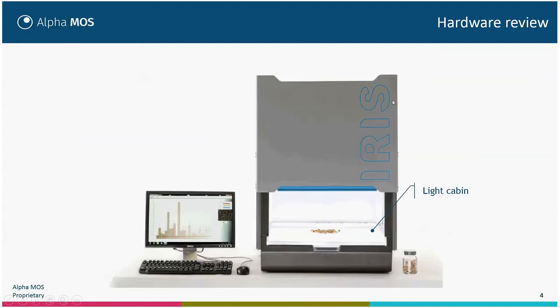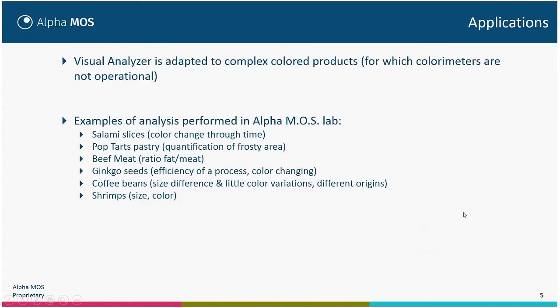This is the IRIS Visual Analyzer. We have a light cabin in which we can put a sample. The camera is inside, which takes pictures that can be treated using the computer with the AlphaSoft software. The Visual Analyzer is adapted to complex colored products for which colorimeters are not operational. We will not analyze one unique color, but the composition — a mixture of different colors in a product.